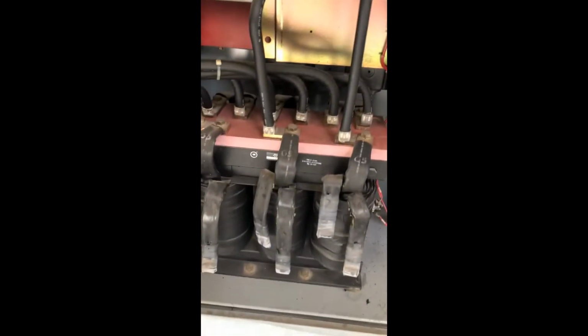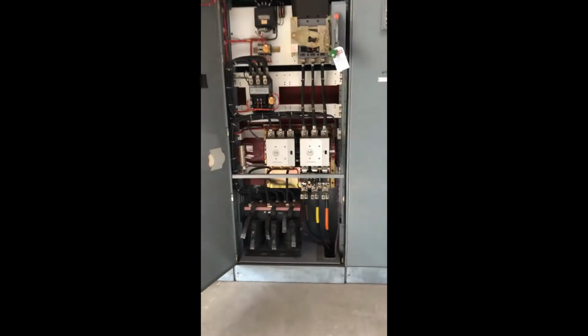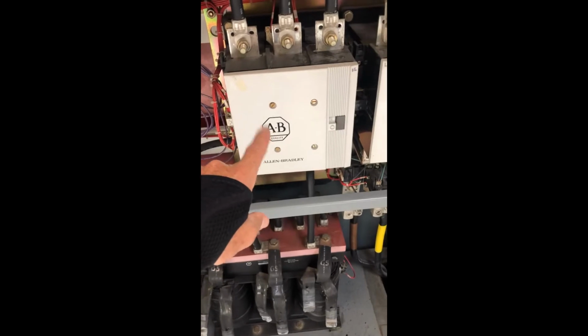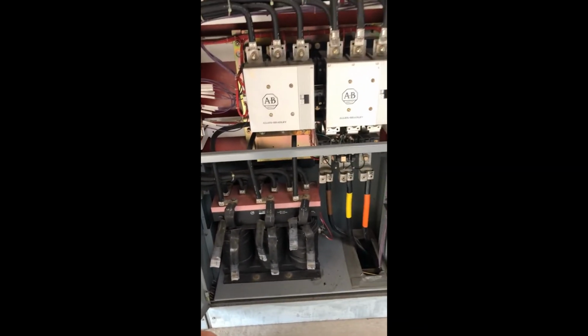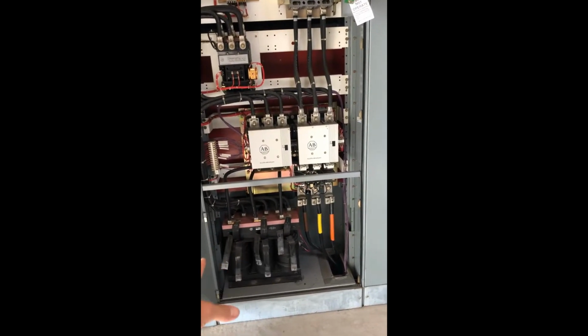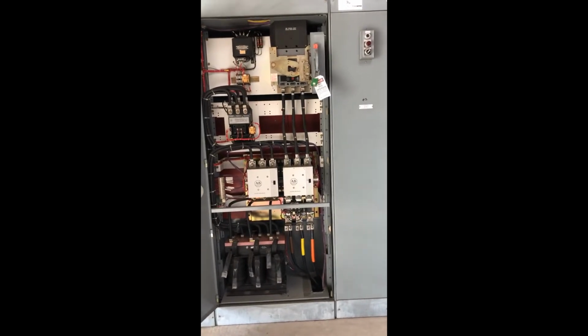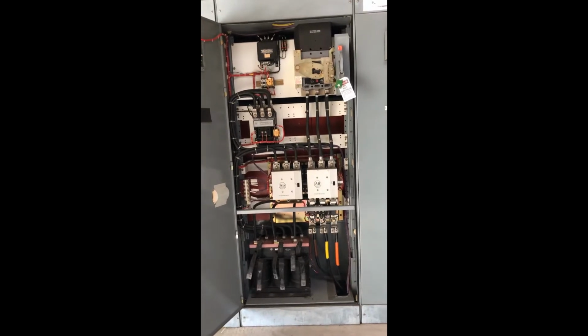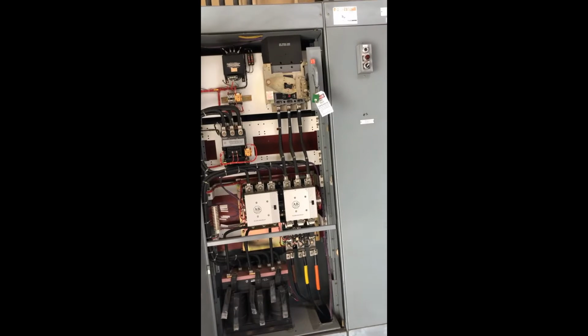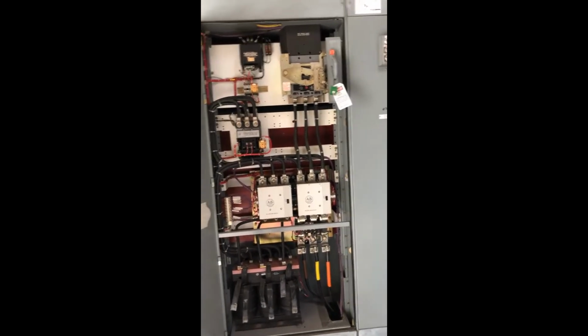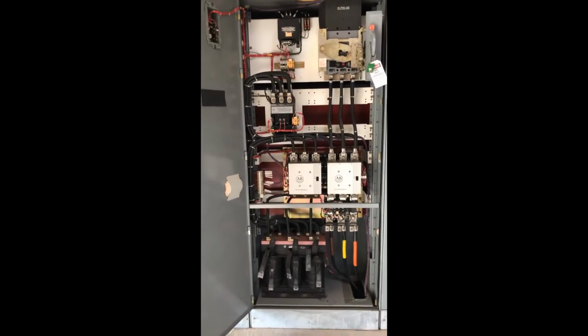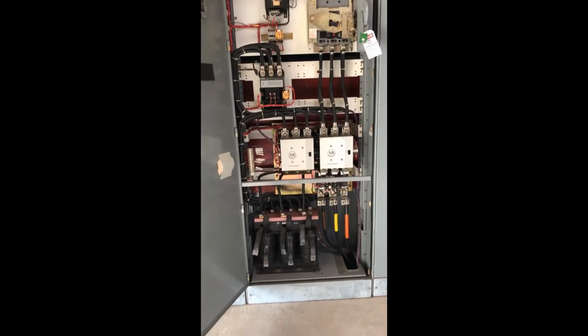Okay. Here's the transformer. So the way this thing works is when you go to start this motor, power is routed through this contactor right there, and through the transformer. So a lower voltage is applied to the motor by running it through this transformer, and that'll get it wound up, get it going. And then we have a timer right here that's probably going to do that for about 8 seconds and give it a good jump, a good rotation. And then after it times out, that starter on the left is going to open, and the starter on the right is going to close, and it's just going to put full voltage to the motor. So that is a soft starter. It reduces the inrush current by initially starting the motor with a lower voltage that's supplied through a transformer.